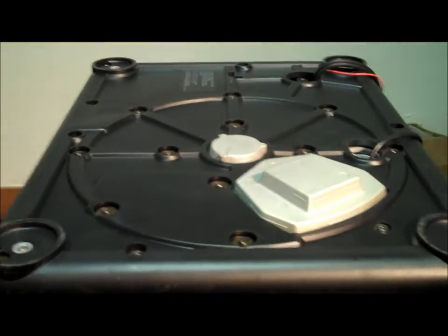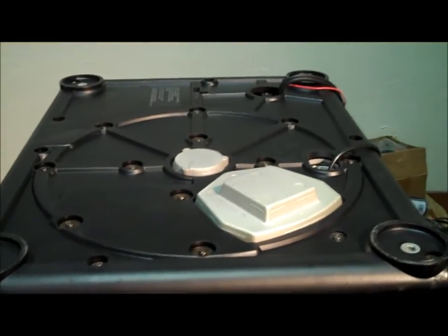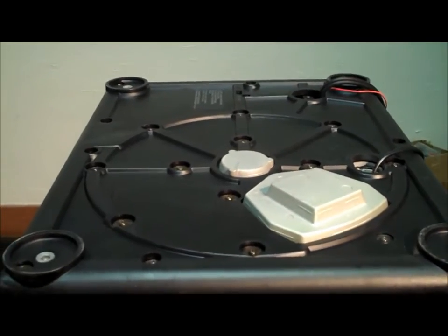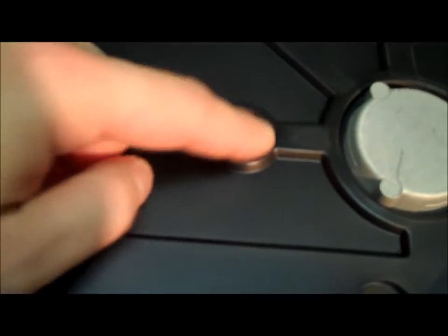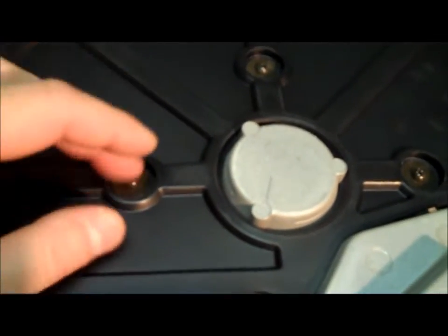You can see that there's a ton of screws here, which is always a really big pain to work on manually, so I'm going to use a power driver. Actually, one little tip: do not use the power driver when you're closing it back up, because these screws right here are pretty fragile, and the heads end up breaking off. What's going to happen is the head breaks, the washer comes off, and you have a broken screw piece in there, and you'll never get it out. So just a little tip.